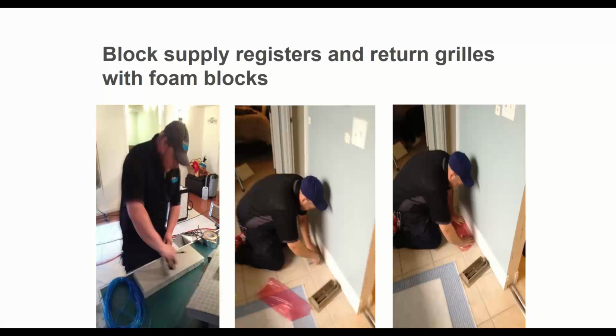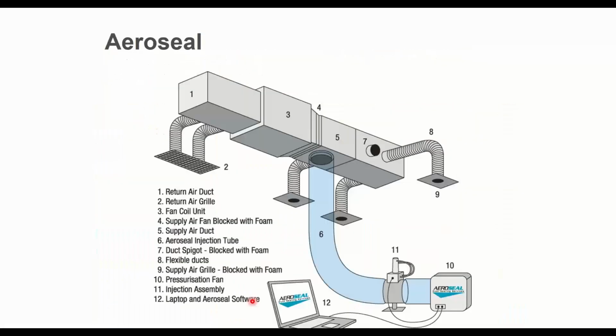The reason we use the foam blocks instead of just using tape like we did for the test is that the duct sealing test is done at typically pretty low pressure. 50 pascals, 25 pascals is the standard for residential. 25 pascals is 0.1 inches of static. It's a pretty low pressure test. When we seal the ductwork with Aeroseal, we're going to start low and keep ramping it up as the ductwork seals. And we're going to finish at 2.5 inches of pressure that we're pushing into that duct system with the Aeroseal equipment. So if we put just tape on the diffusers, it would eventually blow right off as the duct system got tighter and tighter.